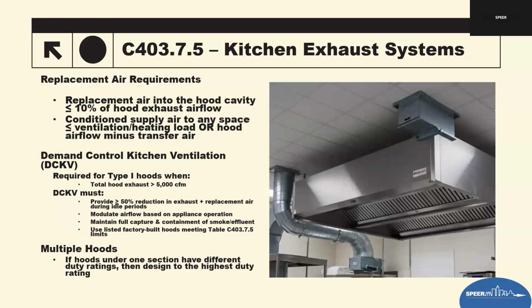Kitchens often run high exhaust continuously, so that DCKV requirement now allows for dynamic reduction of airflow, dramatically cutting heating, cooling, and fan use, especially in restaurants and cafeterias. So, plan review tip here: check total hood airflow. If it meets that and triggers DCKV at 5,000 CFM or greater, confirm the DCKV control in the sequence of operation. Confirm the hood's listing and model certification. Verify replacement air calculations for compliance, and then look for an ERV only if they're allowed under the IMC.